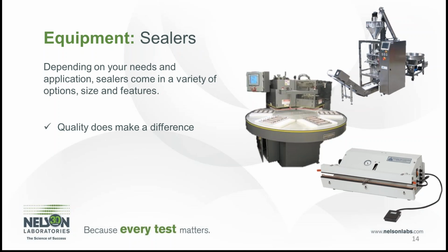Looks at the software, if the sealer has that, to make sure that the software has been validated, that if it rotates or if it has a belt, that the timing of the rotation, the plates for sealing blisters or trays, all are consistent and congruent and uniform so that you don't run into issues when you move into production of them not working properly.